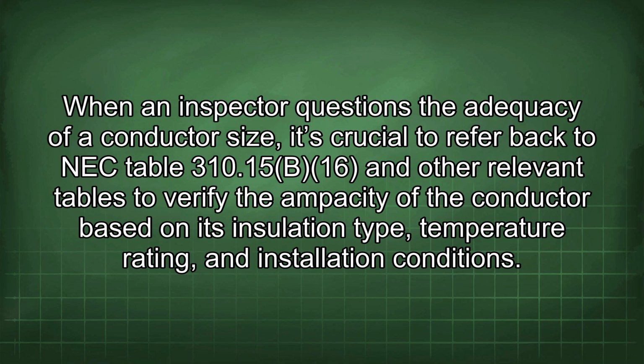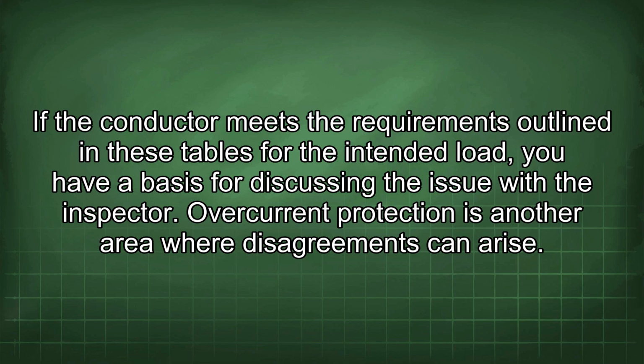When an inspector questions the adequacy of a conductor size, it's crucial to refer back to NEC Table 310.15(B)(16) and other relevant tables to verify the ampacity of the conductor based on its insulation type, temperature rating, and installation conditions. If the conductor meets the requirements outlined in these tables for the intended load, you have a basis for discussing the issue with the inspector.